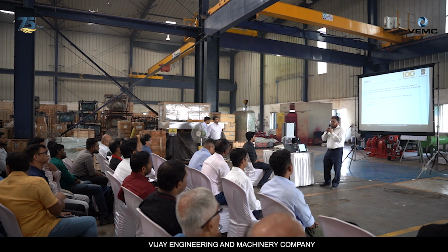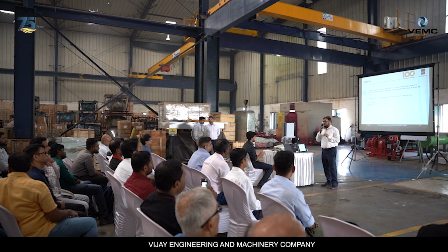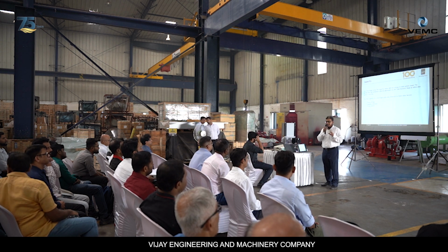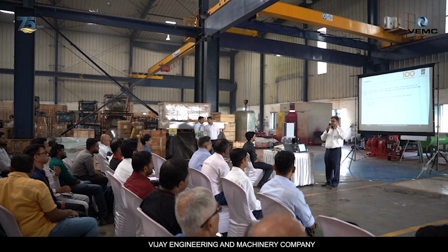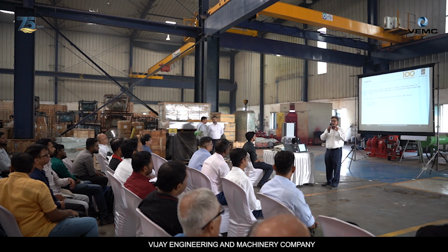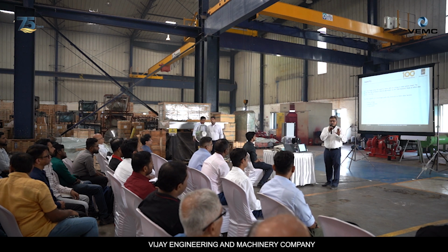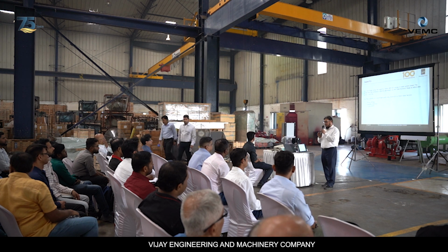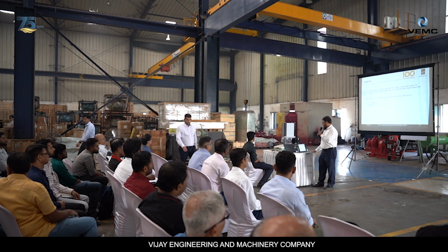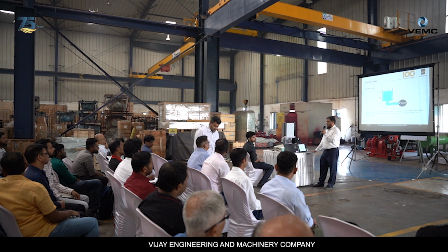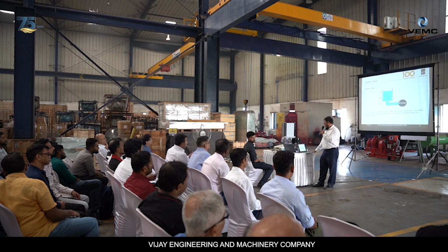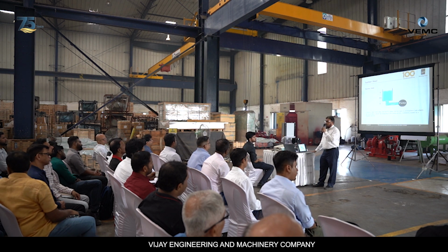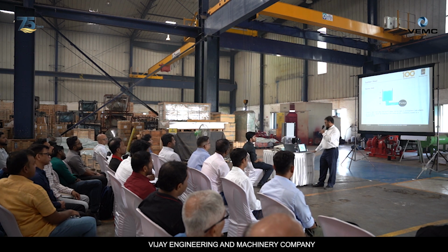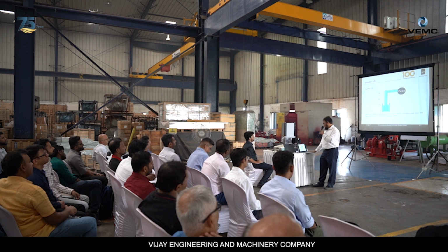Two things are very important apart from these four categories: one is capacity and another is head. On the basis of these two parameters, head and capacity, we select the pumps, either end suction, split case, or vertical turbine pumps. These are typical of the suction head, where the tank is above the suction level. By gravity, water will come into the eye of the impeller.